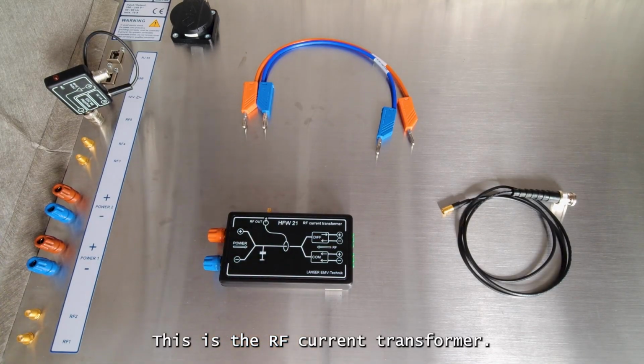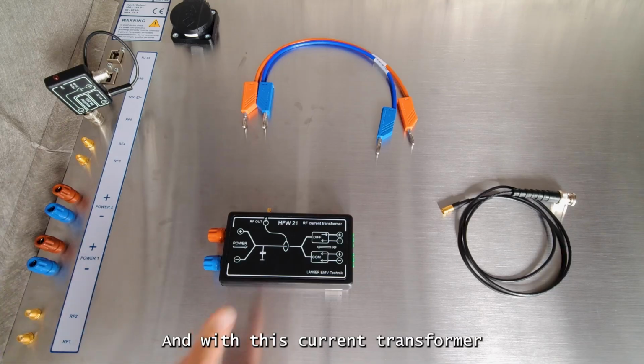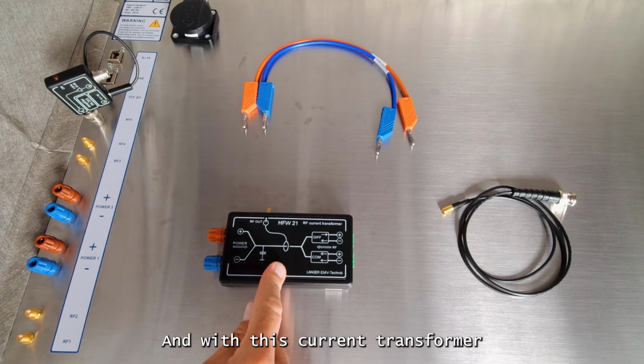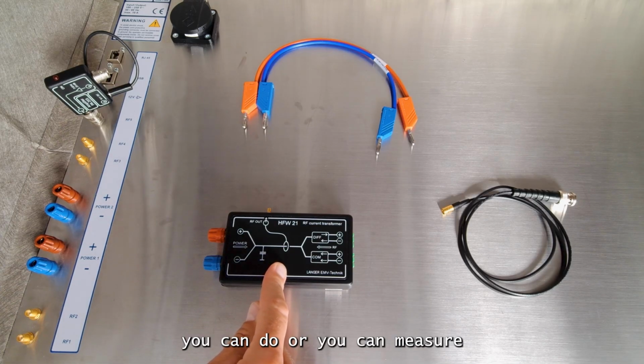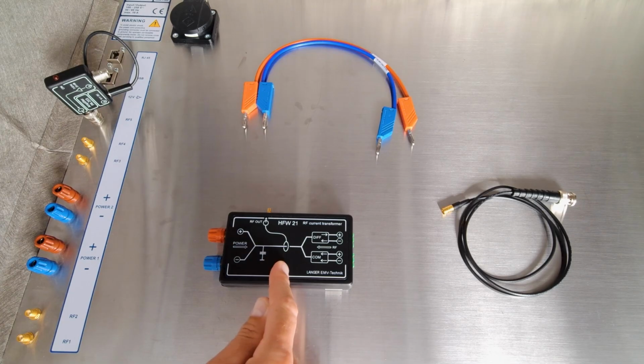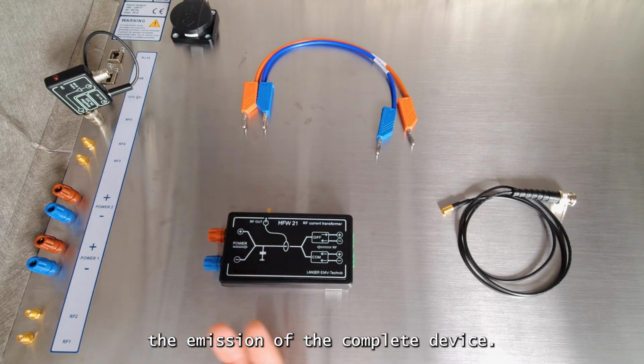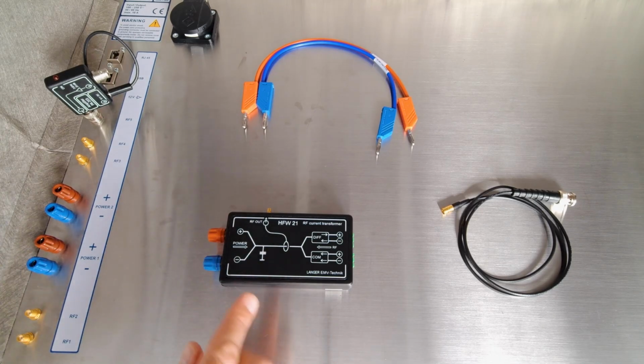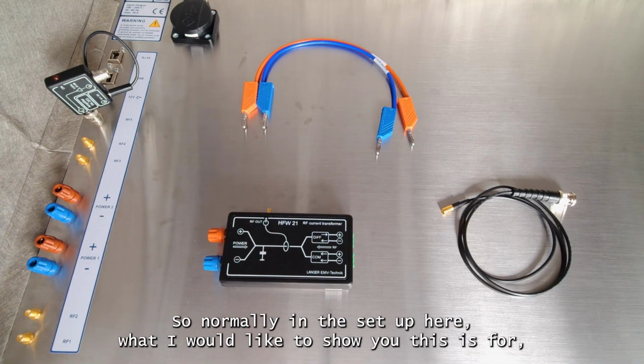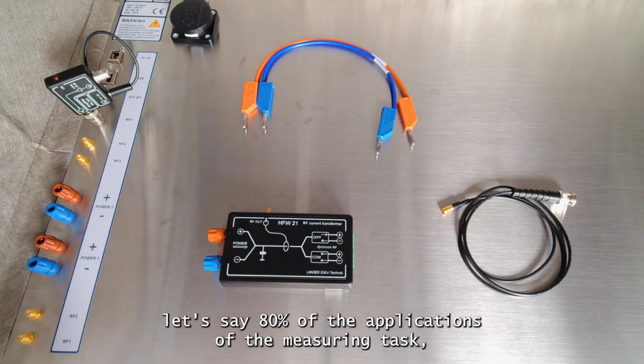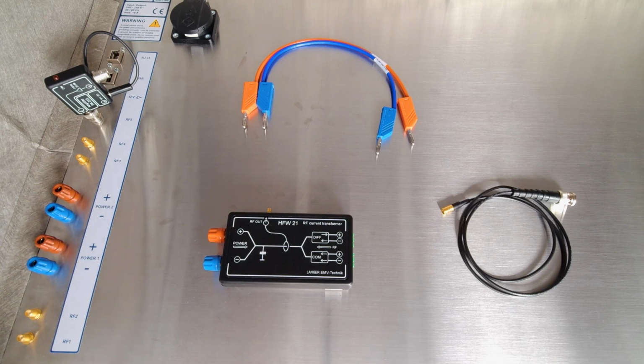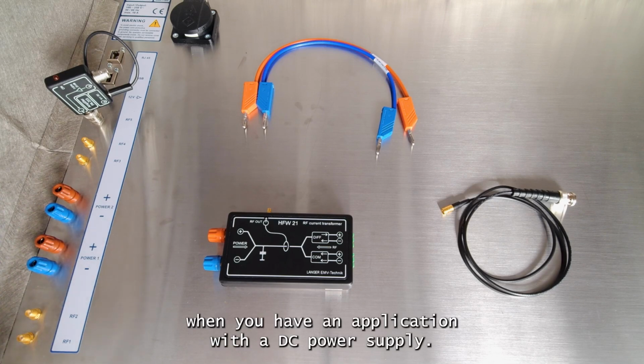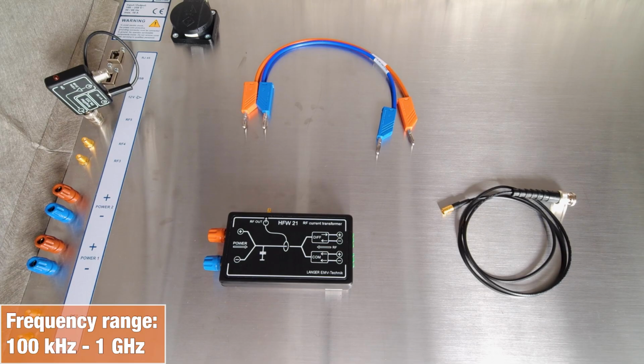This is the RF current transformer, and with this current transformer you can measure the emission of the complete device. So normally in the setup, what I would like to show you here is for, let's say, 80% of the measuring tasks, when you have an application with a DC power supply.